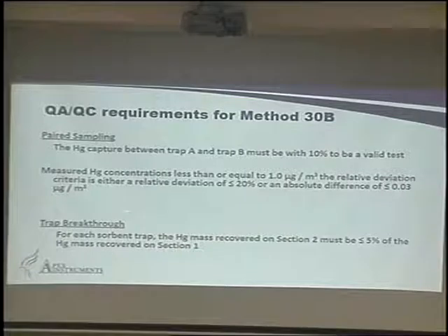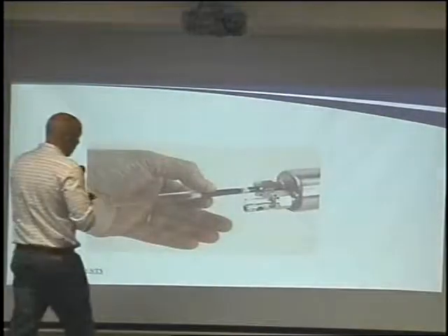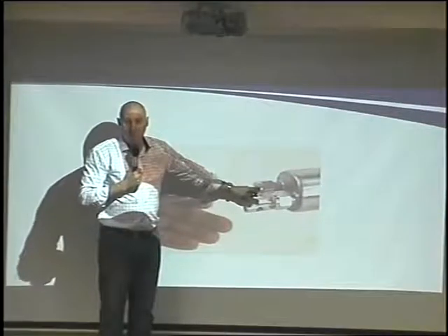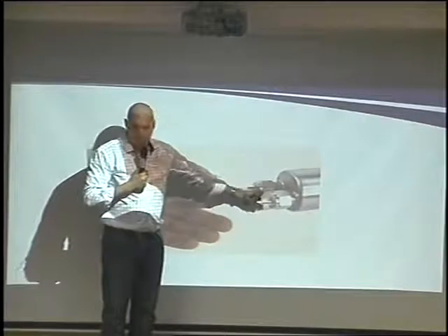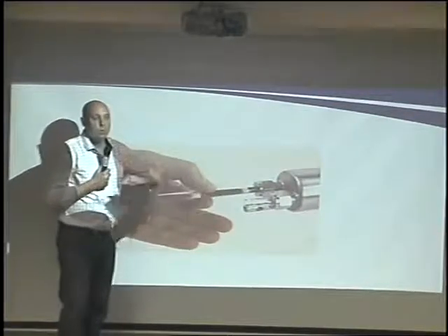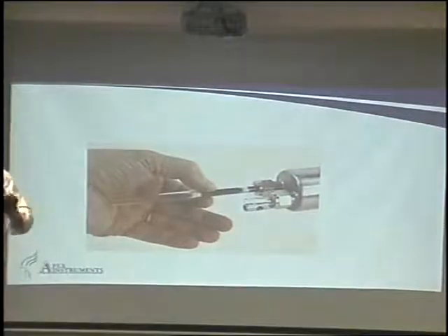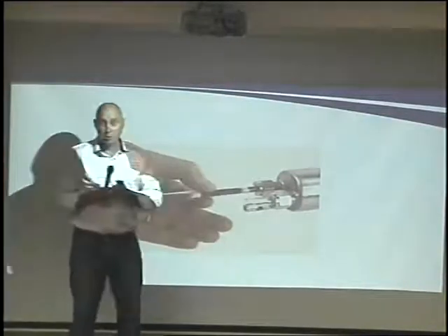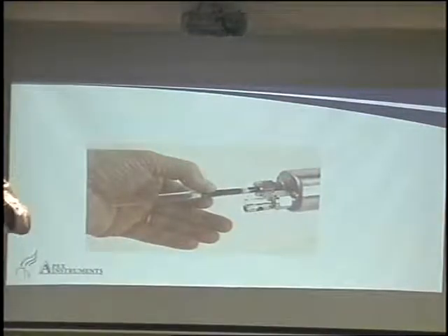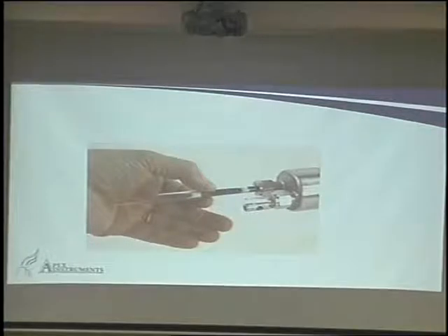And then we talked about this earlier, trap breakthrough, okay? So let me go back. If you have more than 5% of the mercury here than you captured here, your test has failed, okay? Ideally, this second section should be 0, okay? But if it's 1 or 2%, you're still okay. Good test. Anything above 5%, something again went wrong, okay? Do we have a temperature issue? Was it moisture? Things like this. Happens all the time, okay? Happens all the time.